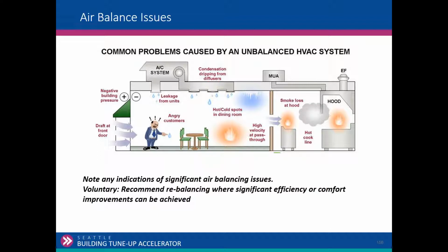That would be something for the owner to follow up, whether that's inadequate makeup air for process exhaust, or overpressurization during economizer mode. So they've overridden their economizer because there's howling, the doors are being forced open from overpressurization, which is a symptom of inadequate relief. So maybe we need to take a look at the relief air system. Or there's an imbalance in the building itself, too much air here, not enough air over here, people complaining about inadequate airflow. Just a recommendation.